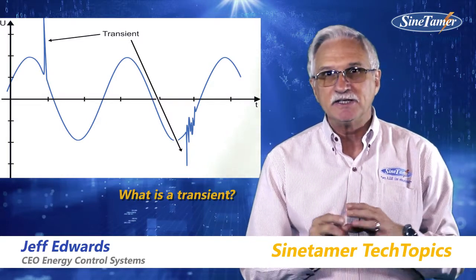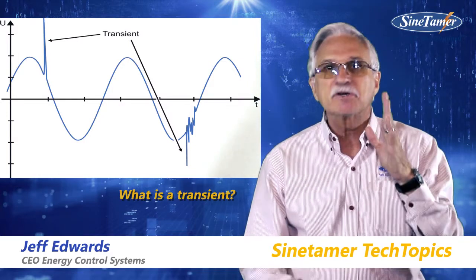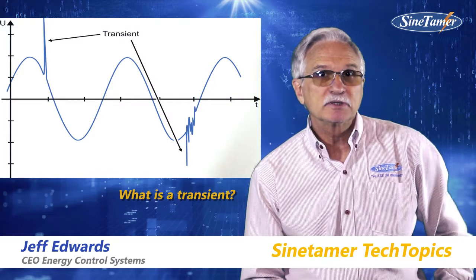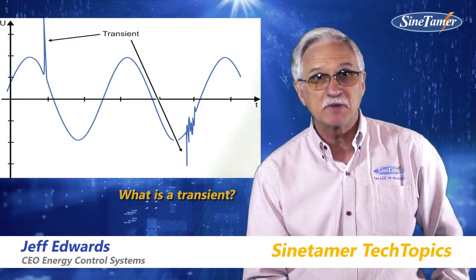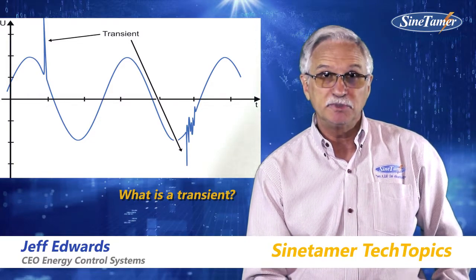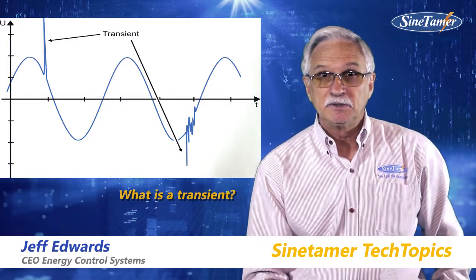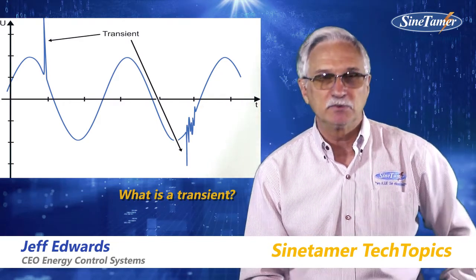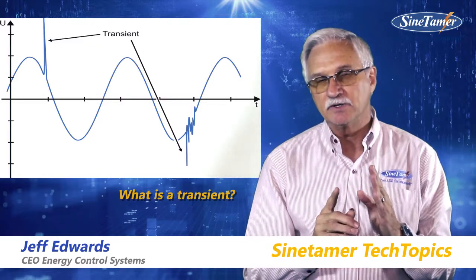By definition, a transient is a rapid excursion of the voltage from the sine wave itself. It can happen typically for a switching transient between 0.2 to 1 microsecond. Larger transients, we might call surges, which could be maybe a couple of microseconds. But the idea is there's a change in the fundamental frequency of the sine wave. When that sine wave changes, that becomes a transient.